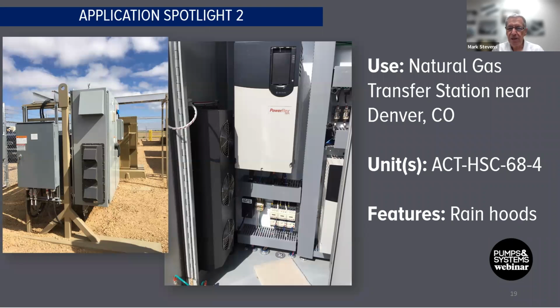This was in Denver, Colorado. These units were cooling a whole series of drives for a gas pump station. A lot of times you may think you need to throw air conditioners in to cool things, but just moving air and conducting heat through those center plates to cool off the interior temperatures of those cabinets gives enough temperature drop that things operate reliably. The fan coolers also have less that can go wrong, since you're not running a vapor compression cycle, so your mean time before failure is probably a bit higher than something with a vapor compression cycle — not to say that the air conditioner isn't a good solution.